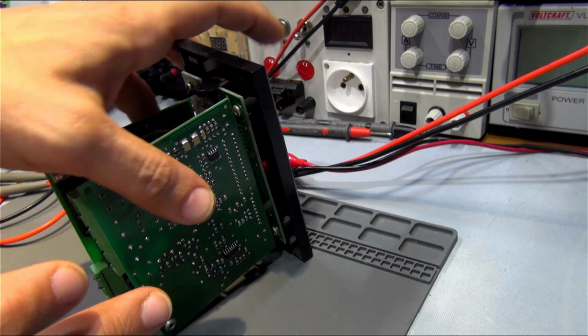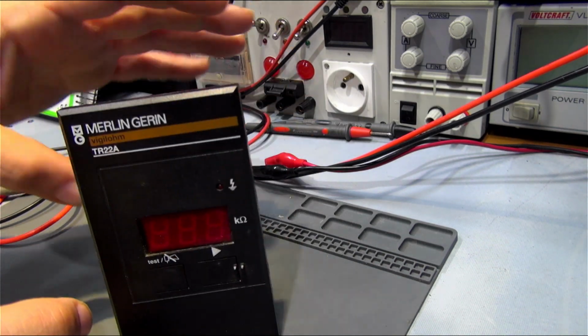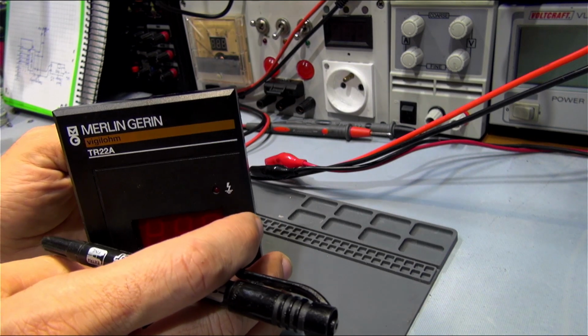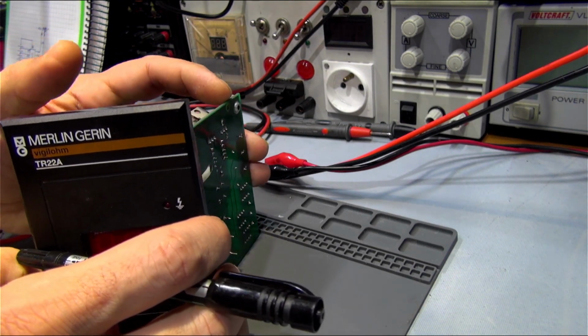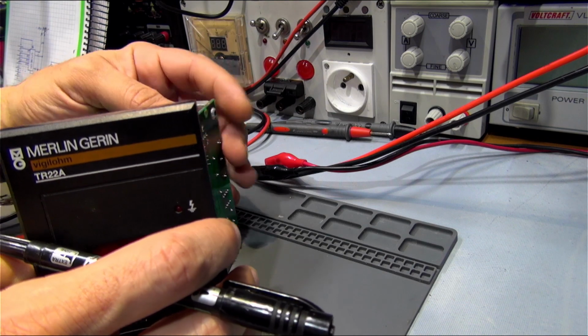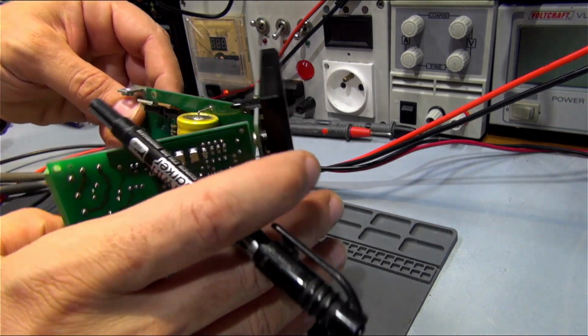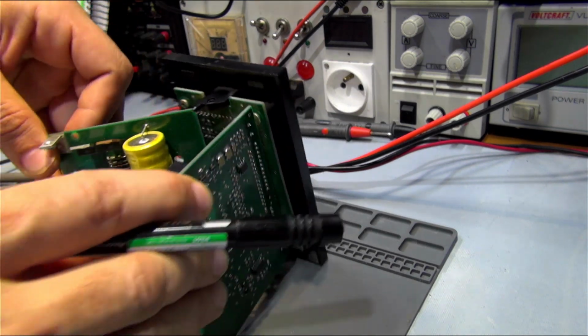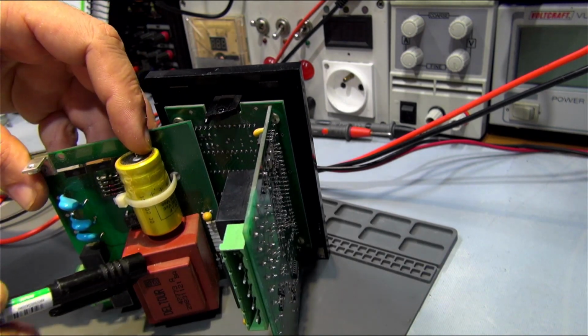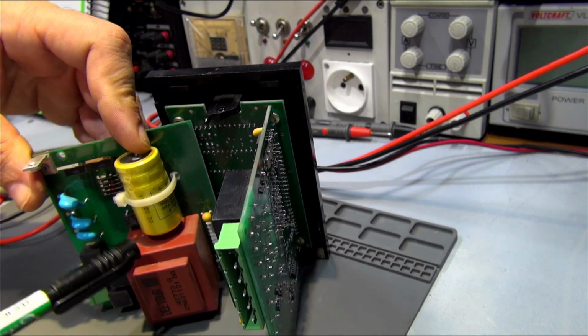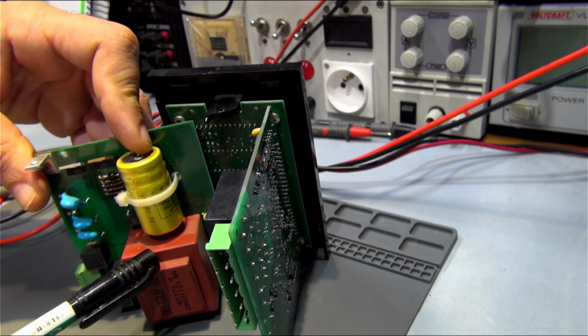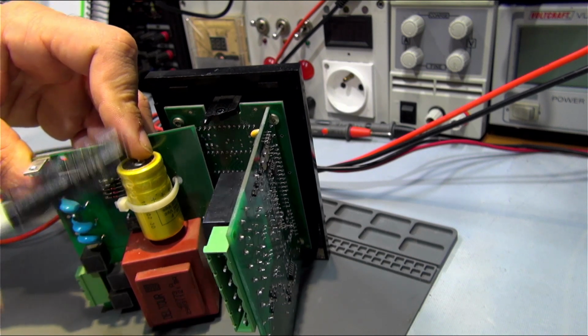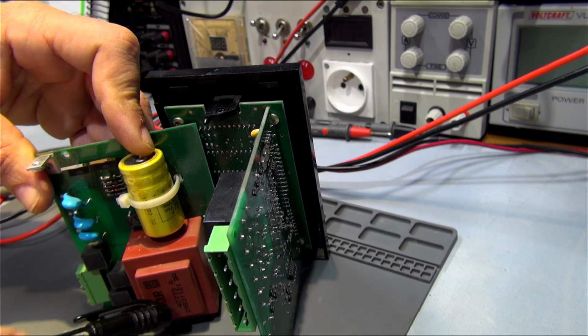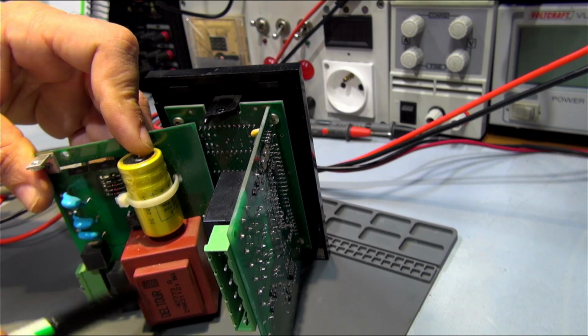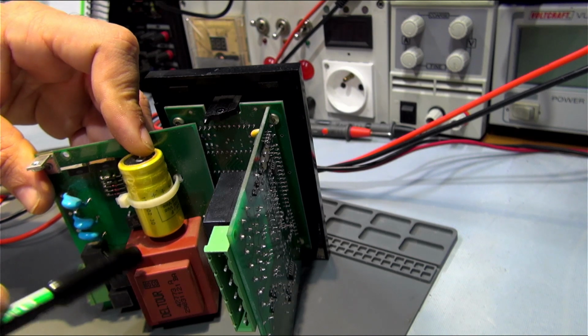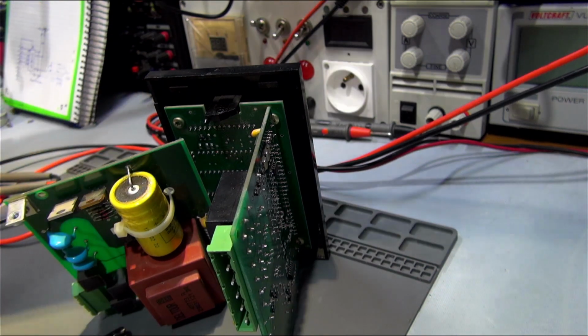In this kind of device, you cannot replace parts like the transformer with an AC/DC switching power supply. You absolutely need a galvanic transformer like this. These kinds of transformers are very difficult to replace for this type of measurement, because you cannot get that kind of galvanic protection otherwise. So let's wait a bit and see where the problem comes from, by making some measurements.